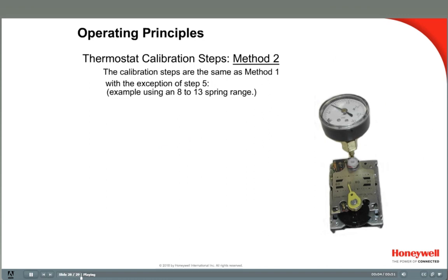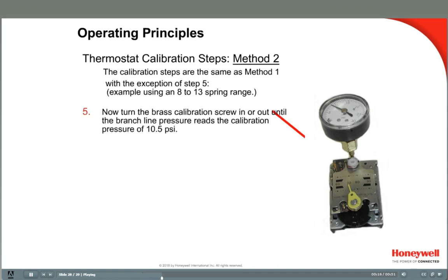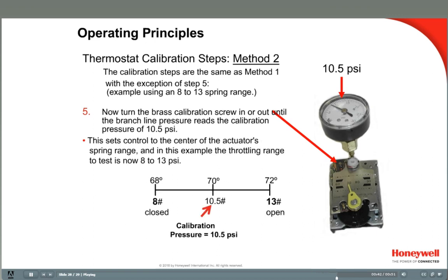The alternate method of calibrating the thermostat — Method 2 — is to calibrate it to the center of the actuator's spring range. In this example, the spring range is 8 to 13 pounds, as indicated on the actuator's product tag. The calibration steps are the same with the exception of the step where we set the calibration screw to the pressure at the middle of the throttling range. Instead, adjust the calibration screw to the pressure midway through the actuator spring range — set the screw until the gauge reads 10.5 pounds, because that's halfway between 8 and 13 pounds. Then verify that the valve or actuator is closed at 8 pounds and open at 13 pounds, as this is the spring range of the actuator.